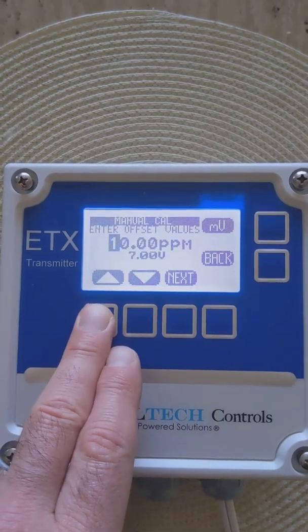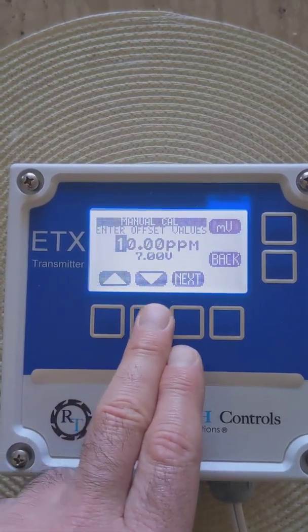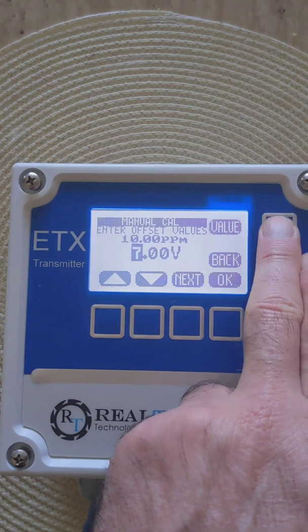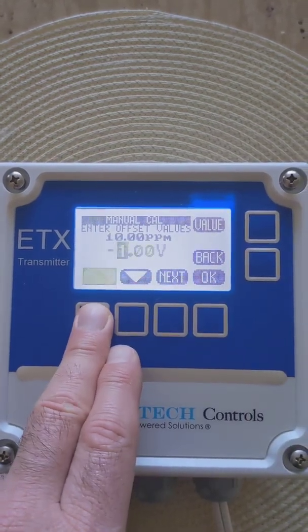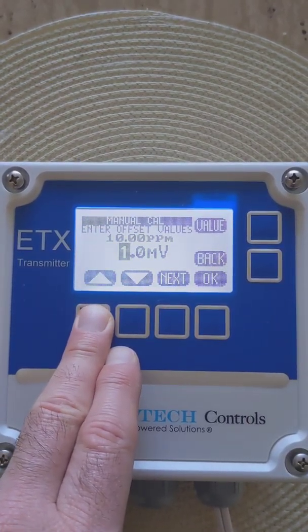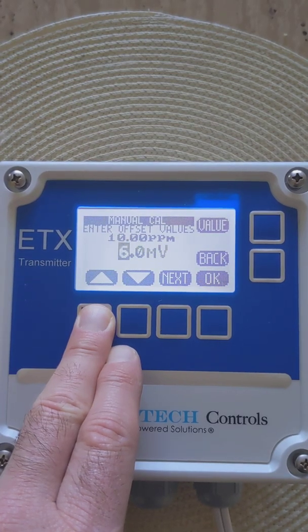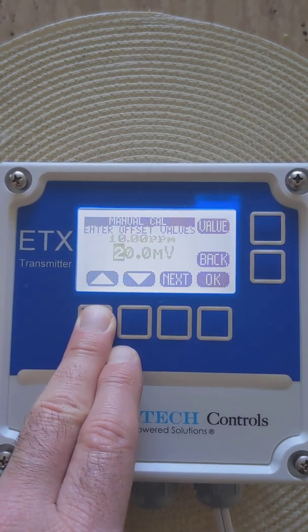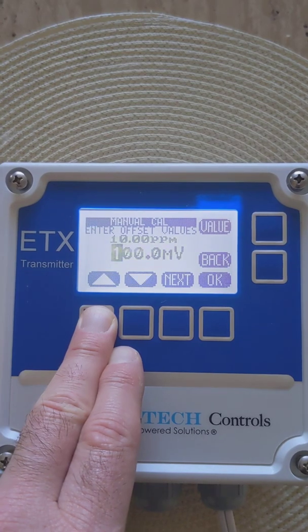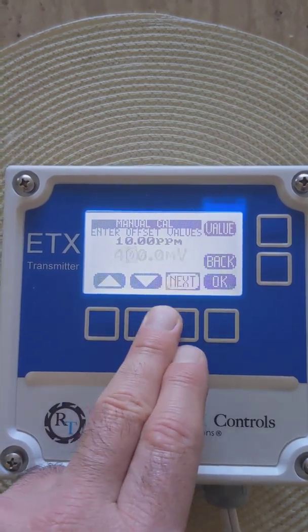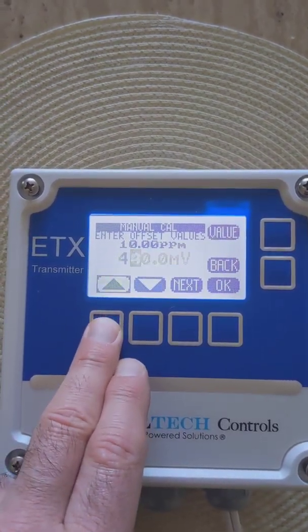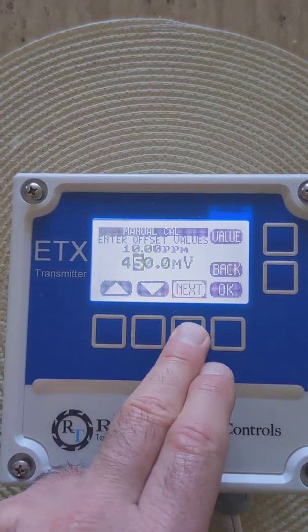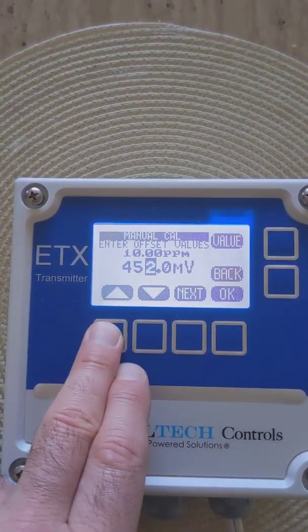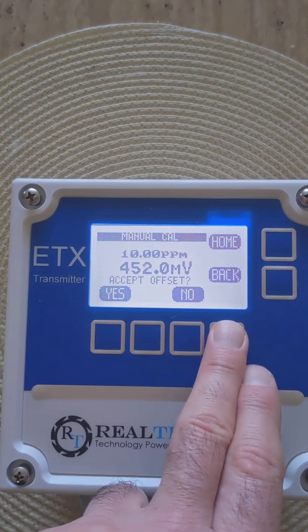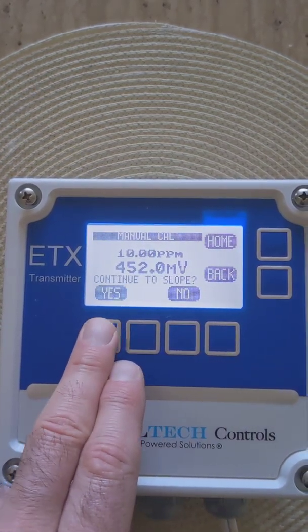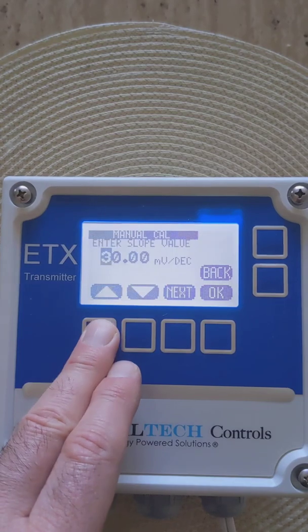I want to start off with the offset. The offset was 10 ppm. I push the millivolt button. So now I want to get to the correct millivolt value, which was 452. If you hold it, it does eventually go quicker. Programmed it in, I push OK. I want to accept it. Do I want to continue to the slope? Yes.